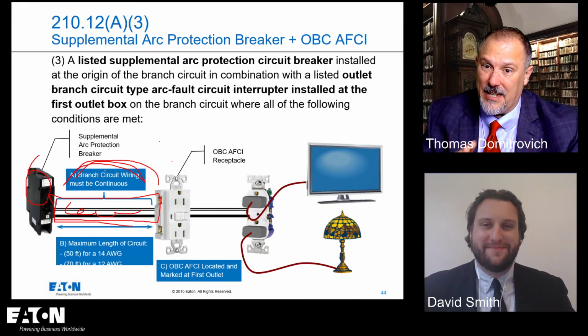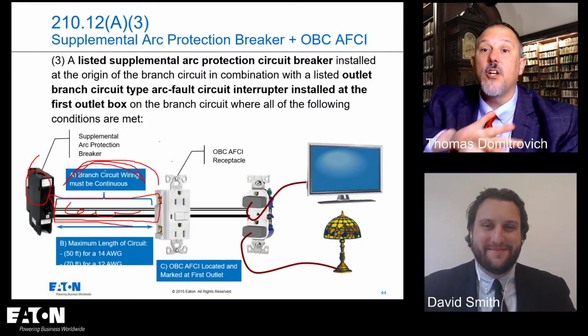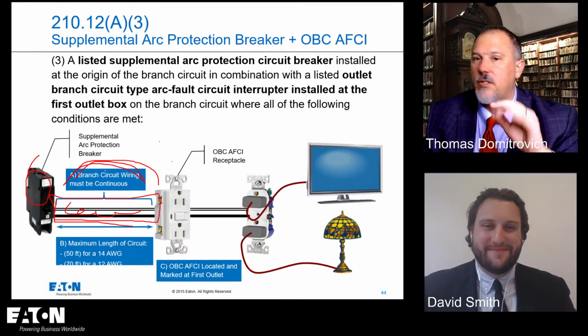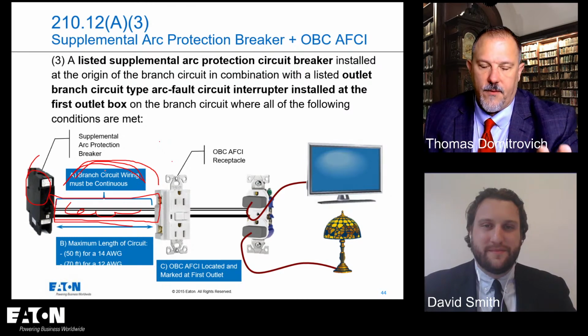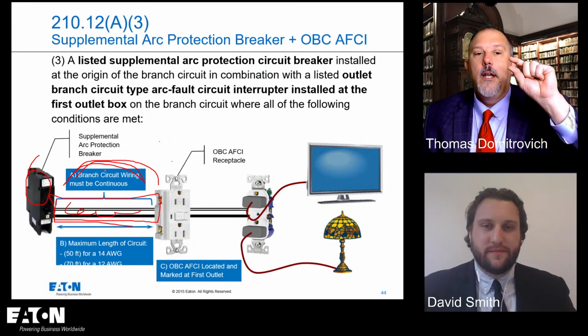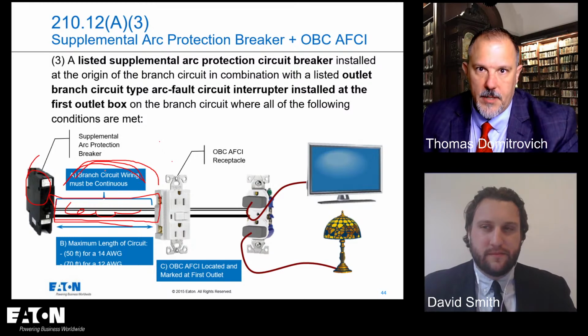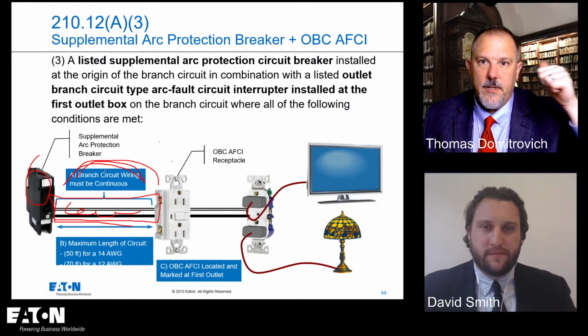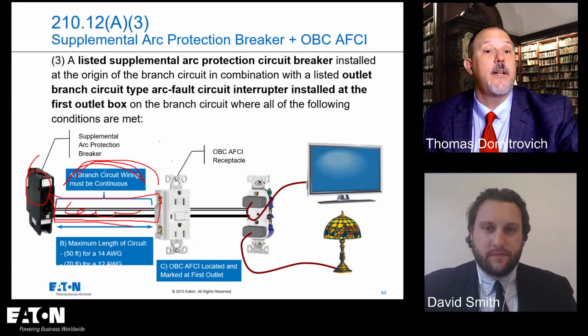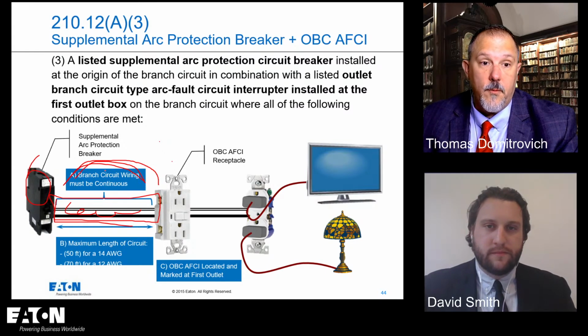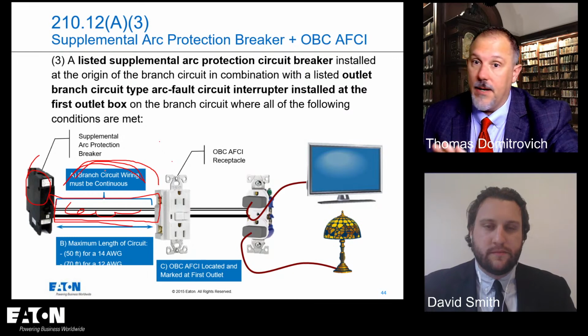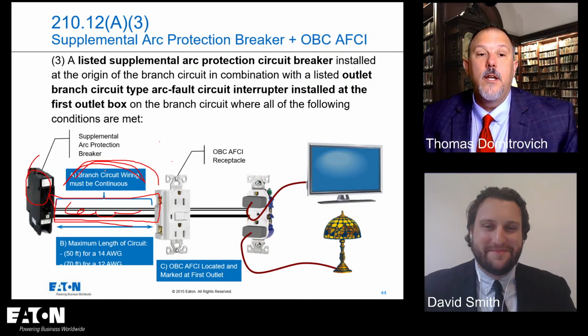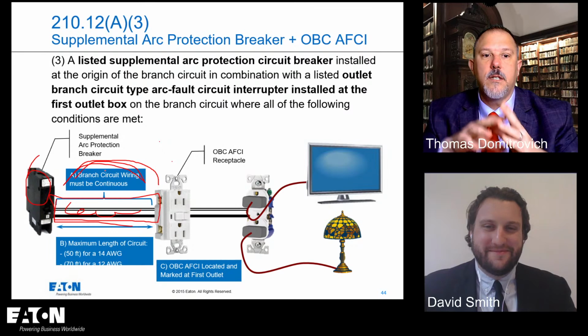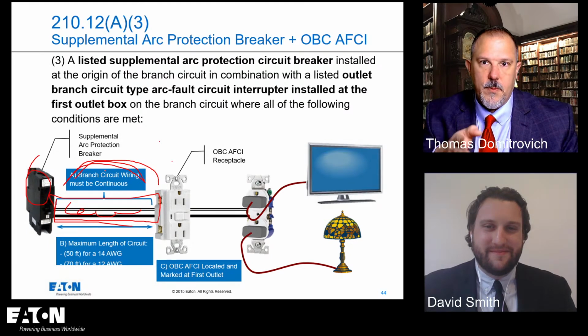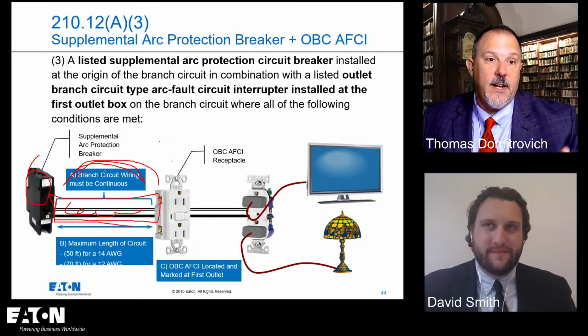Okay? But we've already talked about it's getting power to light that light off of that same circuit. So that's technically not true. But we're going to ignore that. We're going to say, okay, it's just a small amount of current and it's not going to do whatever. So that device arguably can detect a series arc in the upstream, and I could have a good debate and argue whether or not you are actually protecting it, but I'm going to give you that. So that device is stopping the flow of current on a damaged piece of conductor. So technically they're saying I'm providing series arc, but you're not providing parallel arc.